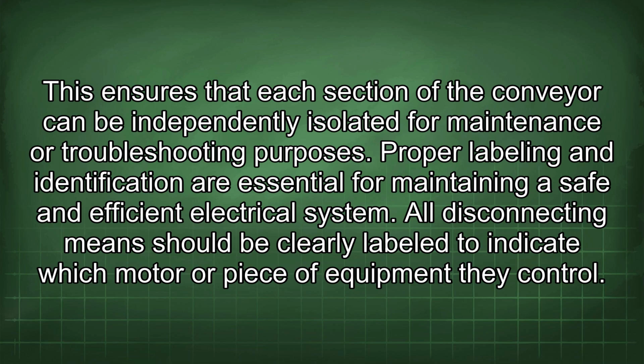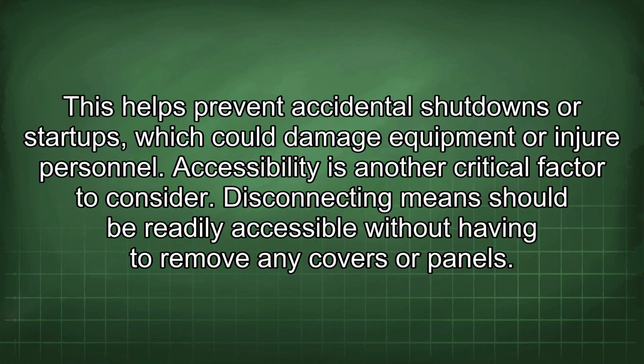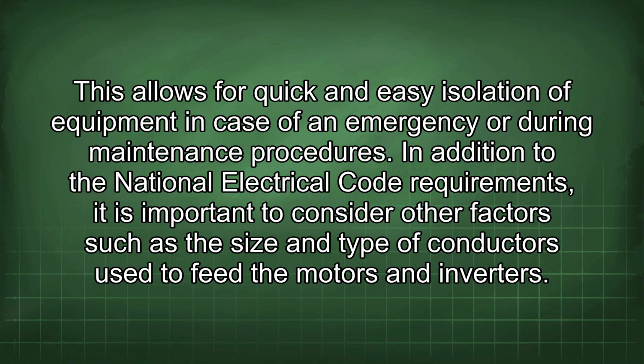Proper labeling and identification are essential for maintaining a safe and efficient electrical system. All disconnecting means should be clearly labeled to indicate which motor or piece of equipment they control. This helps prevent accidental shutdowns or startups, which could damage equipment or injure personnel. Accessibility is another critical factor to consider. Disconnecting means should be readily accessible without having to remove any covers or panels. This allows for quick and easy isolation of equipment in case of an emergency or during maintenance procedures.